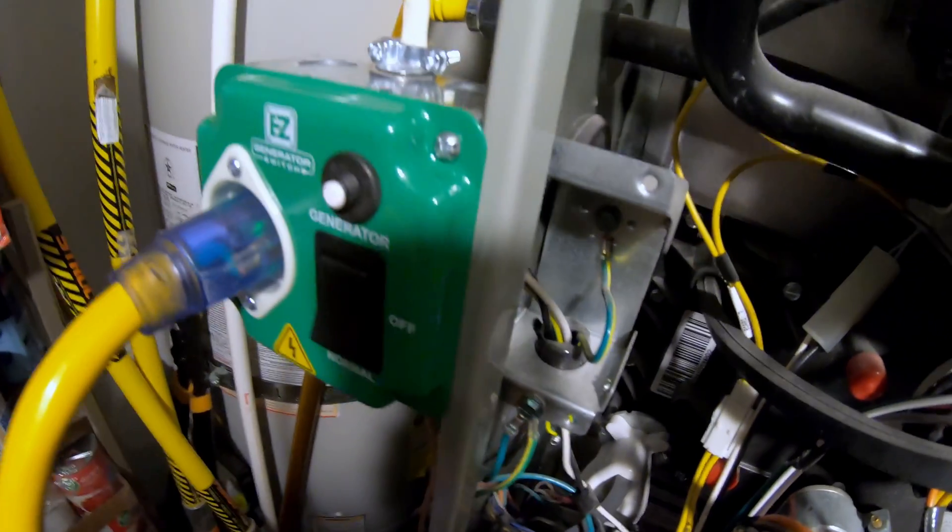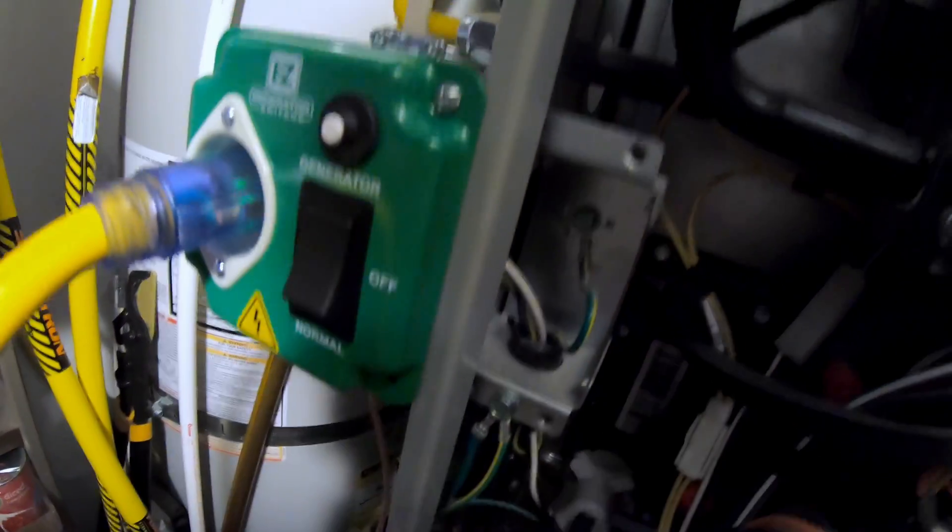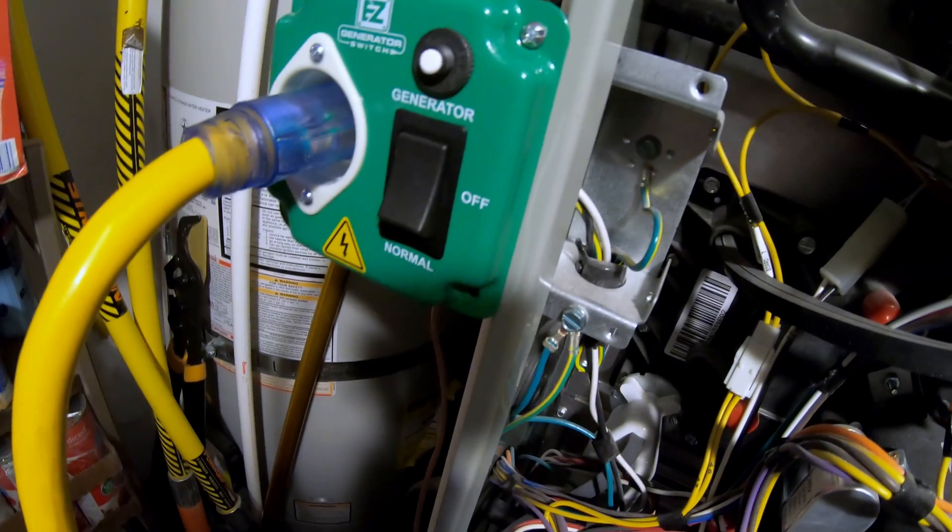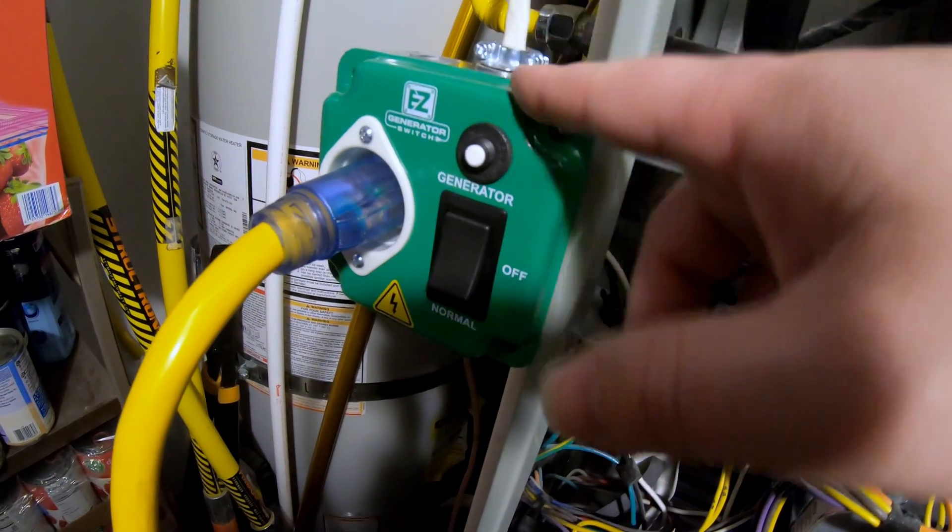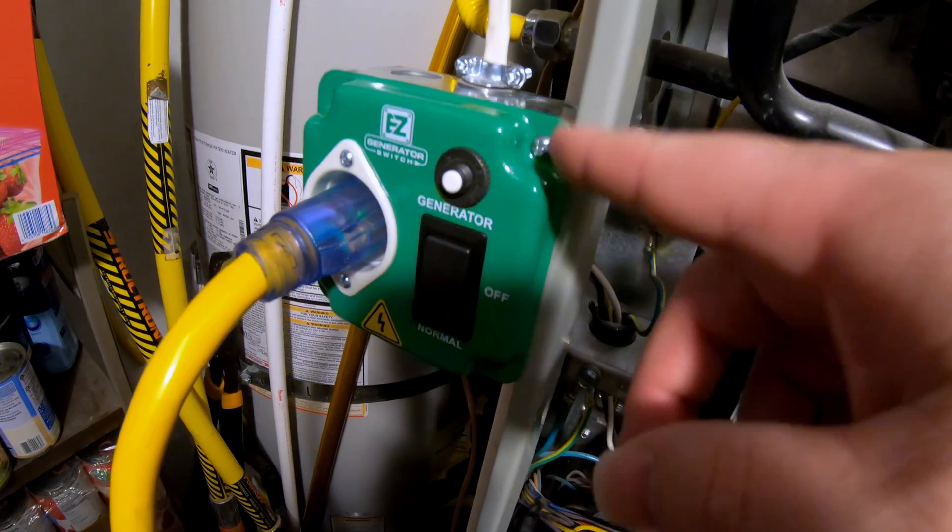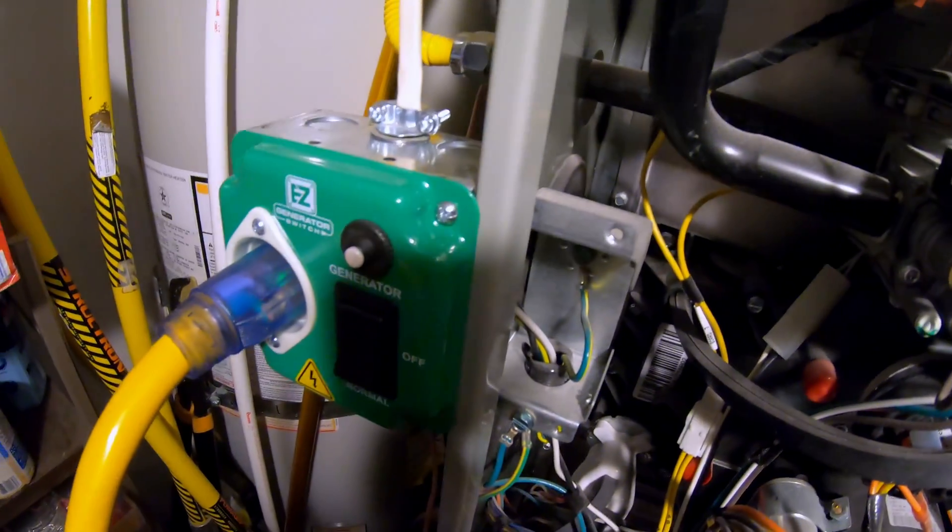That allows you to safely run your furnace when the power goes out. And then when the power comes back on, you just flip the switch down to normal and you're good to go. It also acts as a service disconnect there with an off position. So if you live in a cold area, you definitely want to get one of these because it's worth its weight in gold to be able to run your furnace when the power goes off.